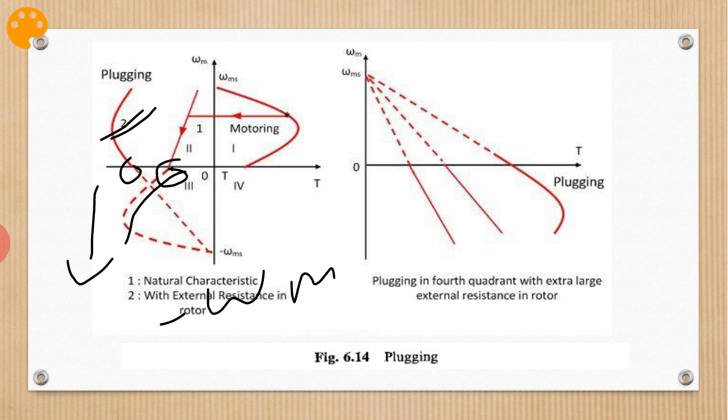And this type of braking is usually suitable for reversing the motor. Such braking is employed for reversing the motor, because as soon as it goes to zero speed, it will be driven in the reverse direction. As the motor is already connected for operation in the reverse direction, torque is not zero at zero or any other speed. The motor smoothly decelerates and then accelerates in the reverse direction.